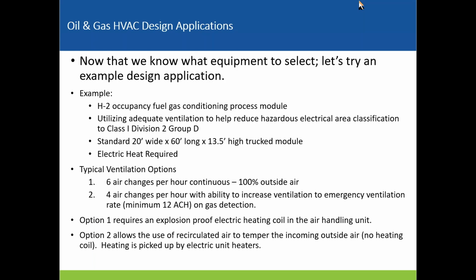I wanted to run through an example. Let's say we have an H2 occupancy, a hazardous occupancy fuel gas conditioning mod. We're utilizing the adequate ventilation that Erik talked about to help reduce the hazardous electrical area classification. We're going with the standard 20 foot by 60 foot by 13.5 foot high truck mod, and electric heat is required. We don't have any glycol heat.